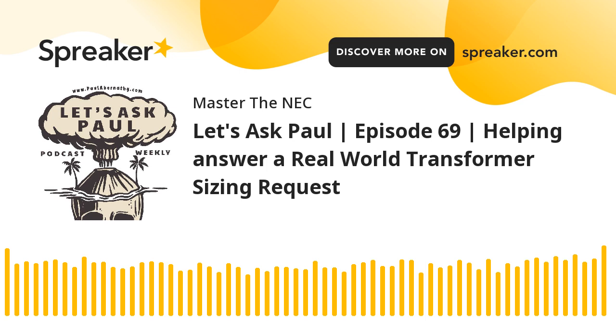If the load is 78 amps, we certainly can have the conductors sized to handle that 78 amps as long as that's what the load is, okay? Then we would be okay. The reason I say that is because you could have had this 45 kVA transformer with a capacity of 125, but I only needed to come off of that for this one HVAC unit, and it pulls 78 amps.